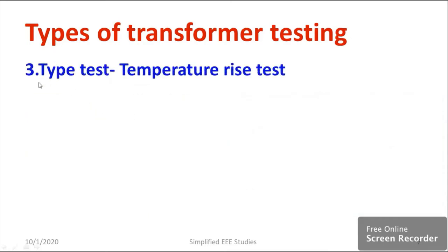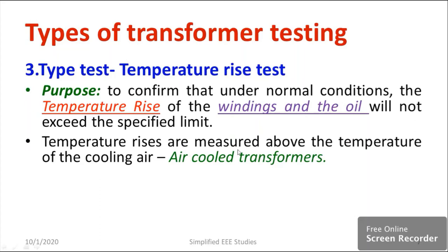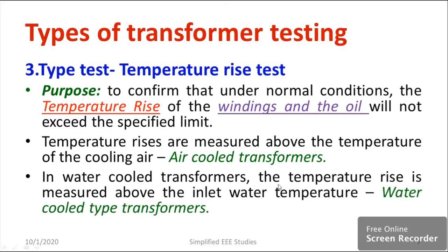I would like to discuss the third type of testing, known as the type test. The main purpose is to measure the temperature rise — whether it is normal or abnormal. To confirm that under normal conditions, the temperature rise of the windings and the oil will not exceed the specified limit. Temperature rises are measured above the cooling air temperature for air-cooled transformers, and above the inlet water temperature for water-cooled transformers.